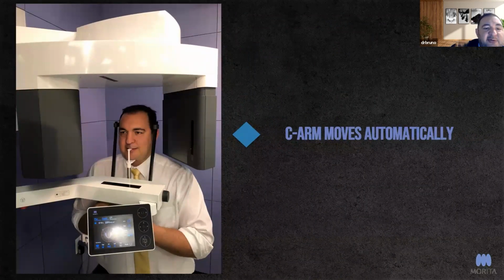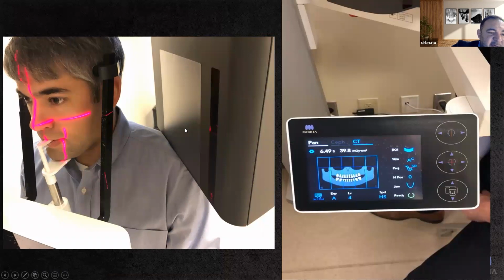What is different about the C-arm of the X800 is that I don't have to change positions for the chin cup. The chin cup only has one position. That's different from the 700, where I can actually turn to the right for position 2 and turn to the left for position 3. On the X800, the C-arm moves itself up. So here is what I mean by that.